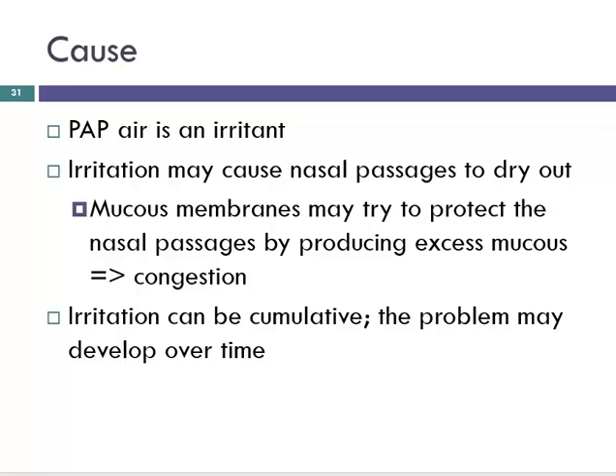It can develop over time and get worse over time. Same thing over the night. So the patient might be fine in the beginning of the night, and you had them set to a good pressure, and all of a sudden, towards the last hour or two of the study, they start snoring again. And you kind of have to go up a little higher in the pressure. Well, it's probably because their body is now responding to the air, and they're getting more congested as the night goes on. So we need a little bit higher pressure to overcome that.